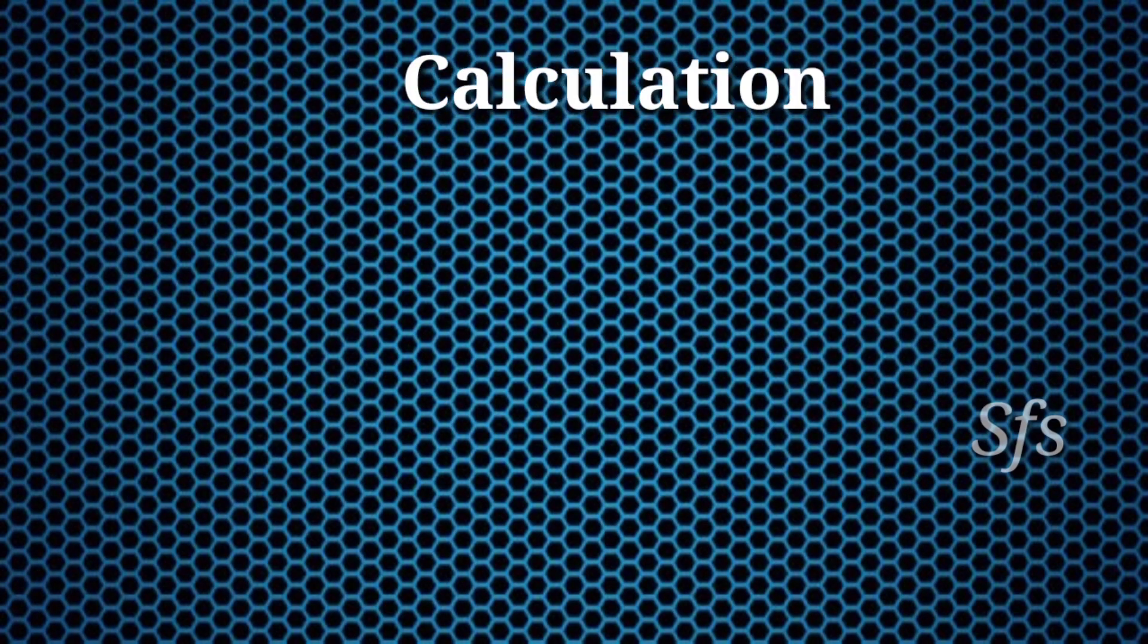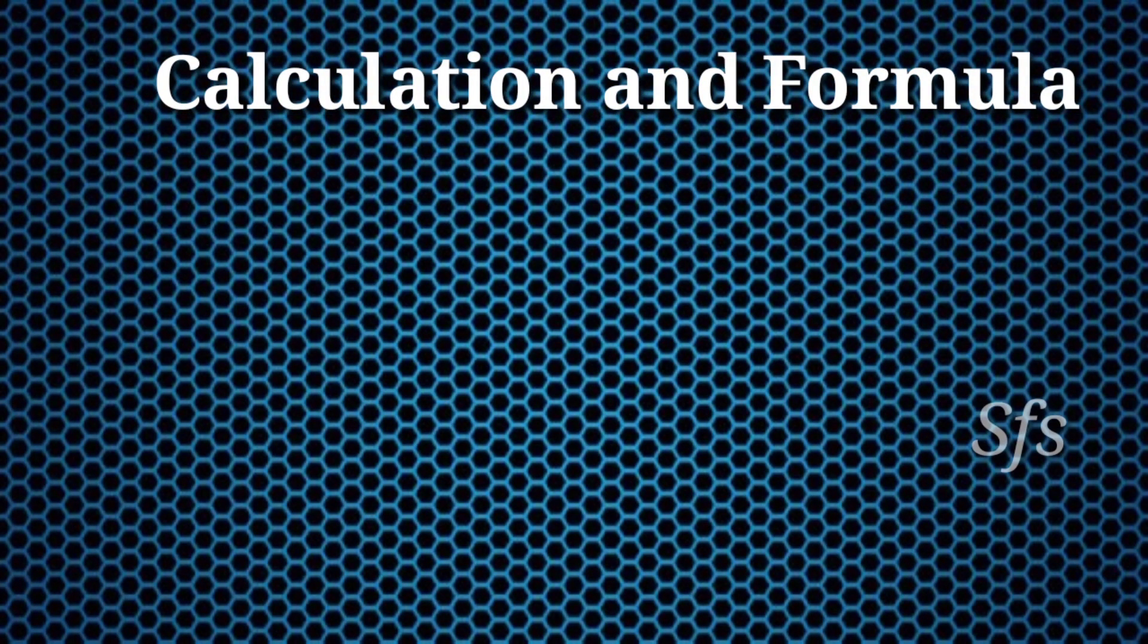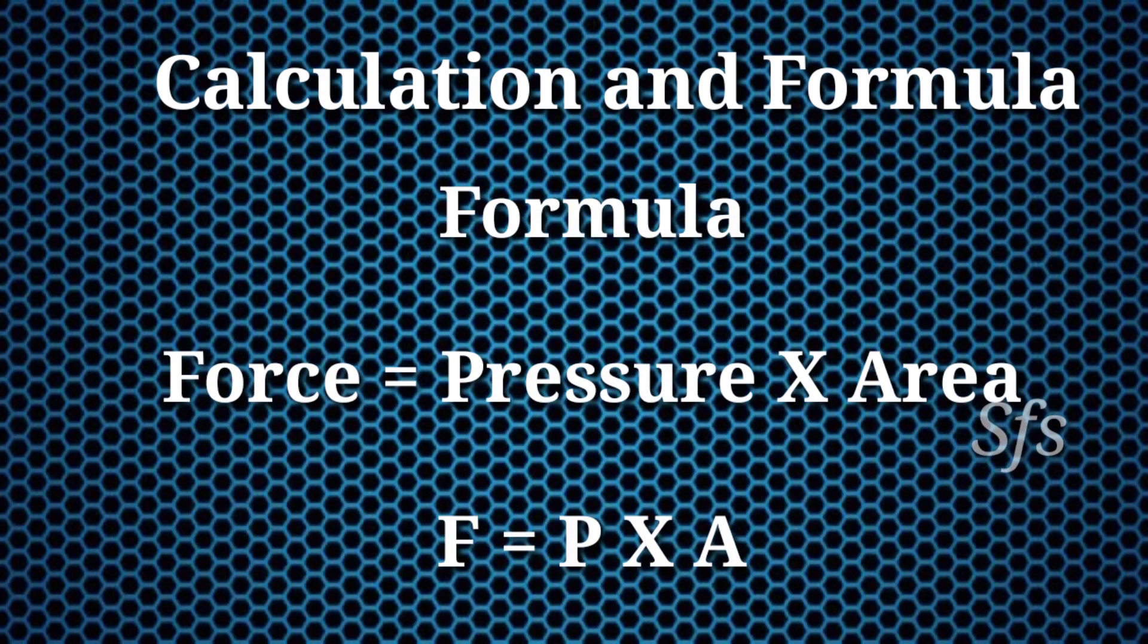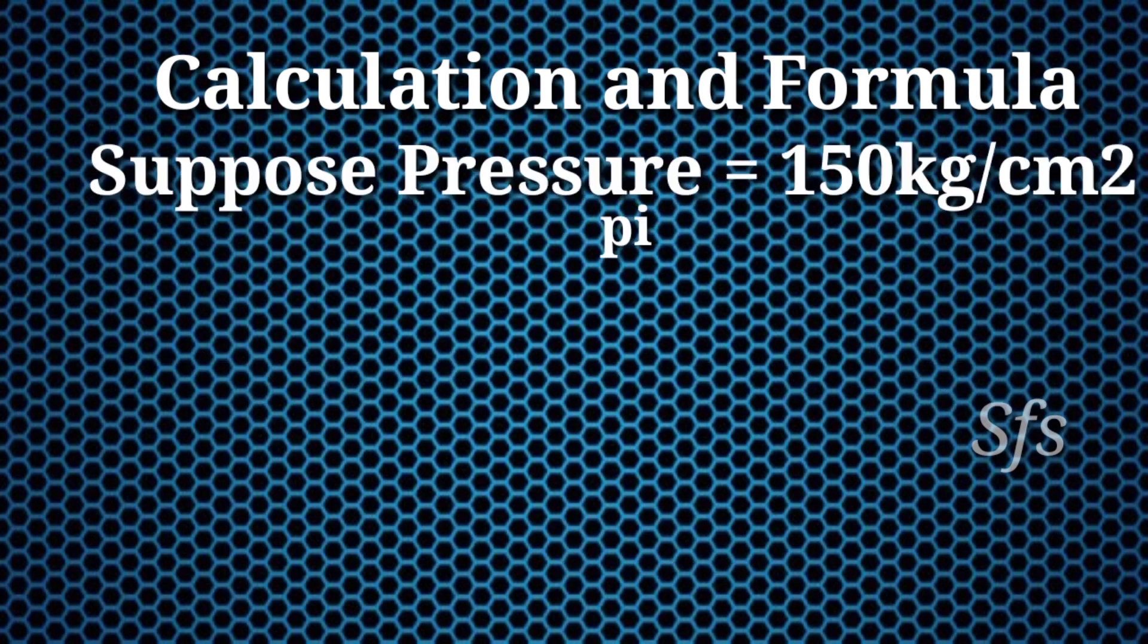Let's start our calculation and formula. The formula for force calculation is: Force equals pressure multiply by area. Pressure is the pressure of the working fluid, means hydraulic oil which is used in the cylinder, and area is the area of the piston.